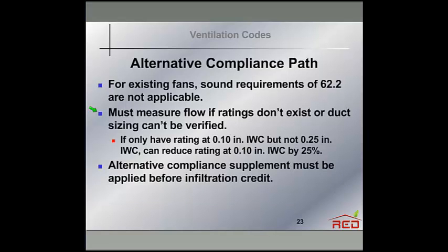There are sound requirements in the standard. If you leave an existing fan in place, say you're going to a house and there's a fan already there, you do not have to worry about sound requirements. But if you are putting a new fan in, the maximum sound for a whole building fan is 1 sone, and the maximum sound rating for a local fan is 3 sones.